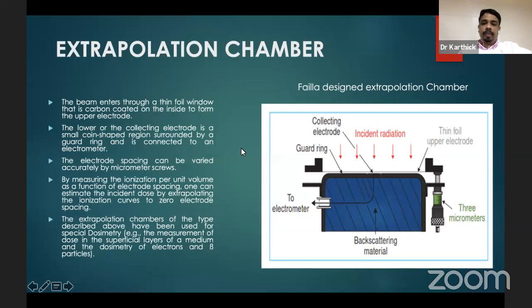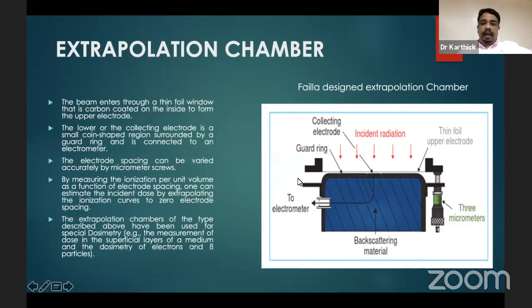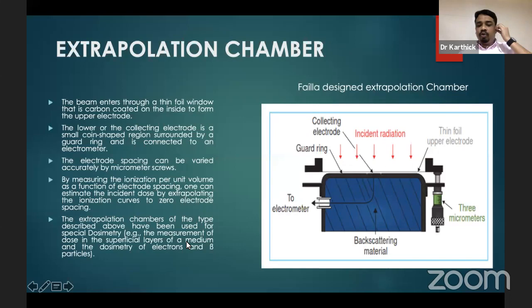Extrapolation chambers are especially used to measure surface dose. The beam enters through the incident window, which is carbon-coated and connected to the guard ring. There is another electrode connected lower down. The advantage of the extrapolation chamber is that we can increase the separation between the two electrodes. By measuring ionization per unit volume as a function of electrode spacing, and extrapolating ionization to zero electrode spacing, we can find surface measurements. Extrapolation chambers are mainly used for special dosimetry — superficial layers, electron beams, or beta particles.